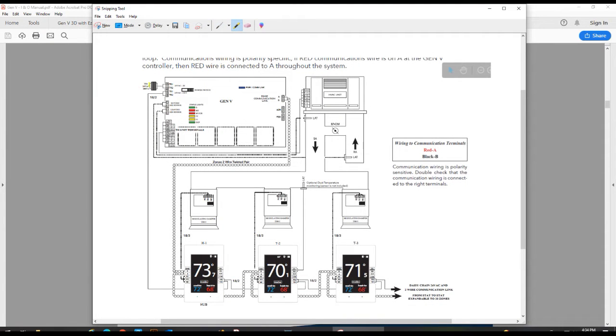As we talked about before, the Gen V controller gets wired in by an independent transformer that wires into TR1, TR2 on the Gen V controller. Do note the system is polarity sensitive, so you want to make sure that your hot leg off your transformer lands on TR1, TR2. We're then going to wire out of the TR1, TR2 terminals using 18/2 thermostat wire and run that to our first zone thermostat. In this case, that is our hub thermostat. And we're going to land the wires on TR1, TR2 and continue that daisy chain all the way through until we dead end at the last thermostat tied to that Gen V controller.